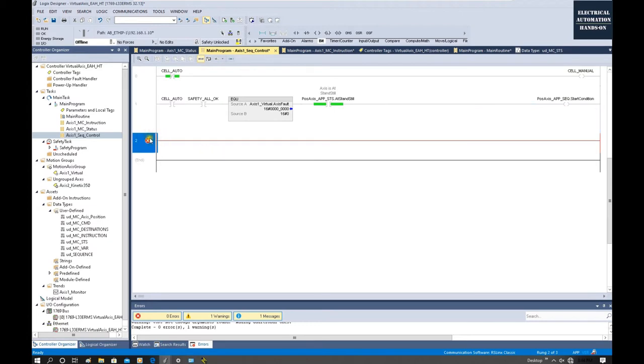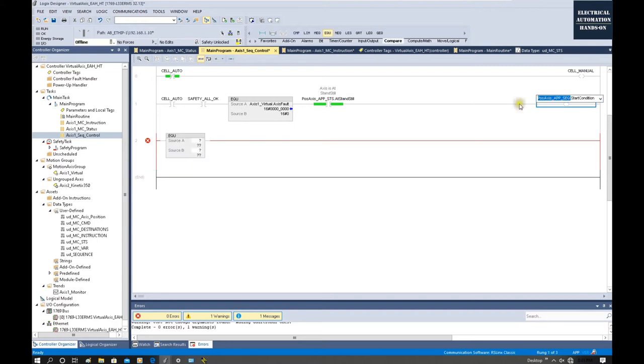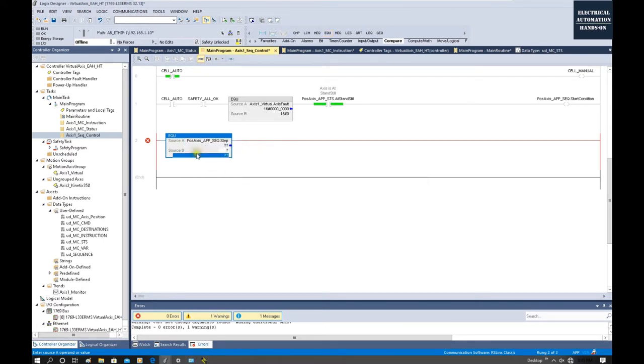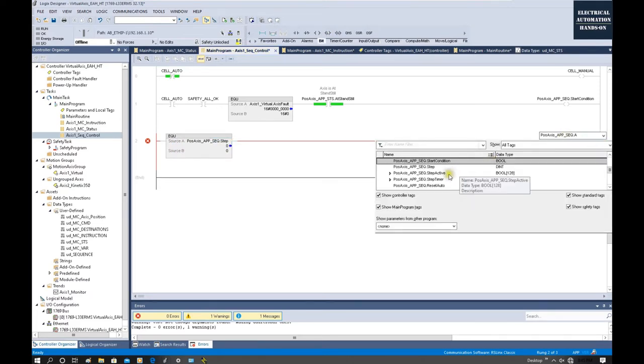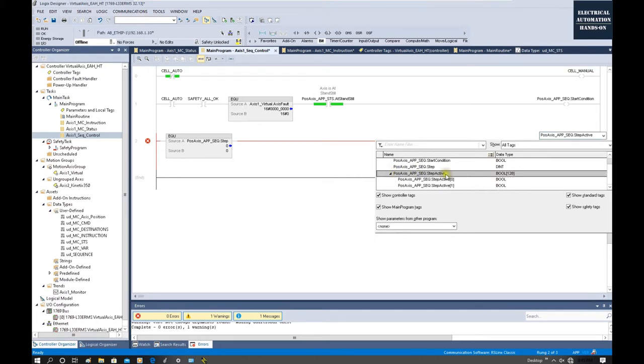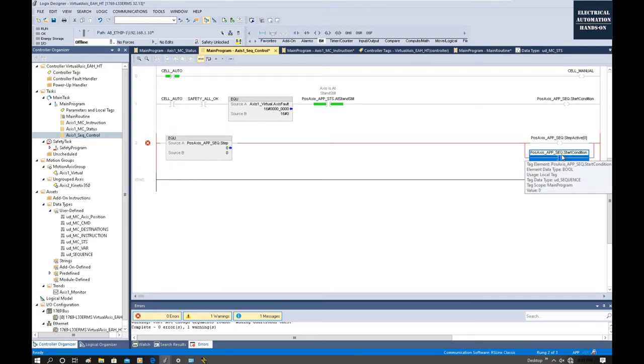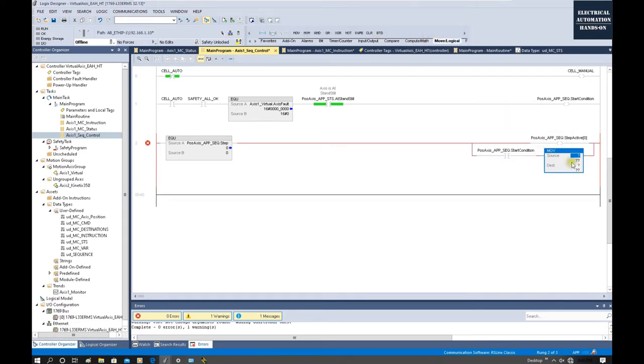This is the first step. At the beginning, the sequence step number equals zero. So at step zero, the step active bit for index zero is set. If the step equals zero and the start condition is on, we can move to the next step by advancing the step number to one. This is the initial step.